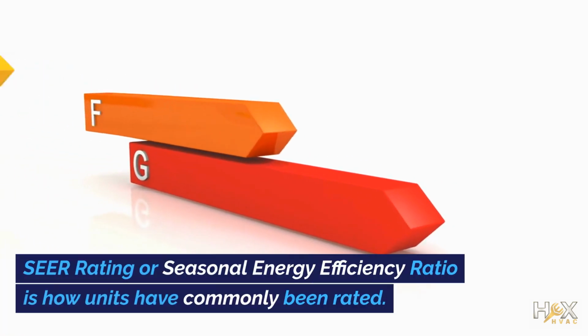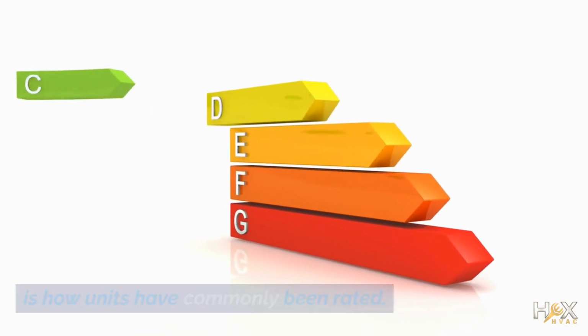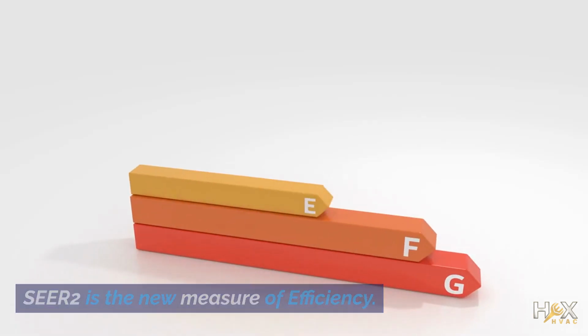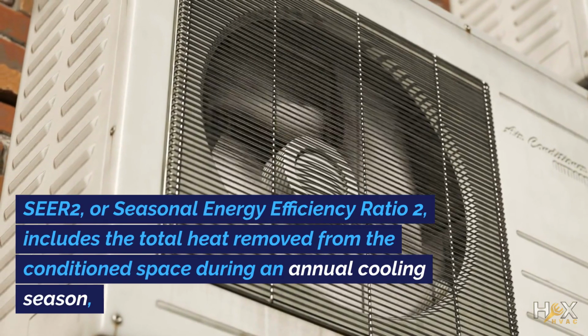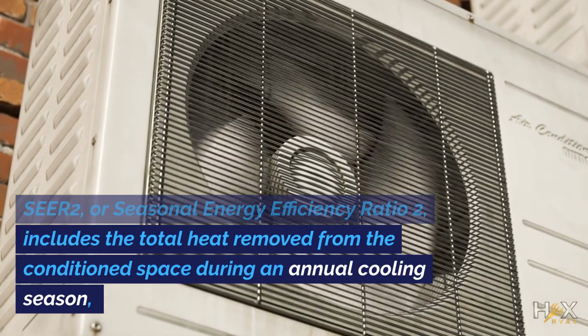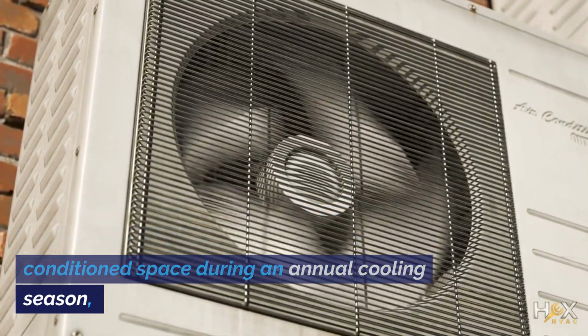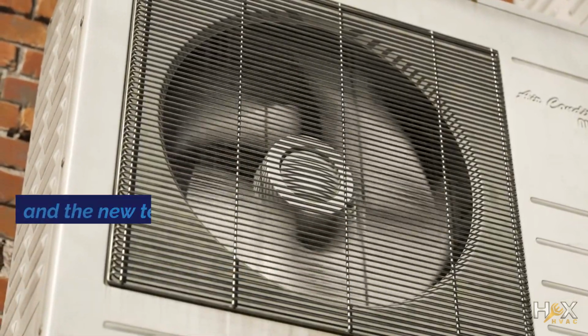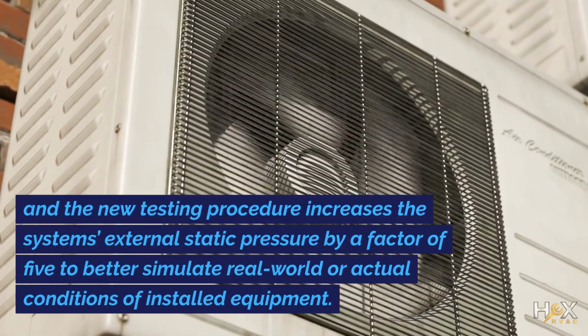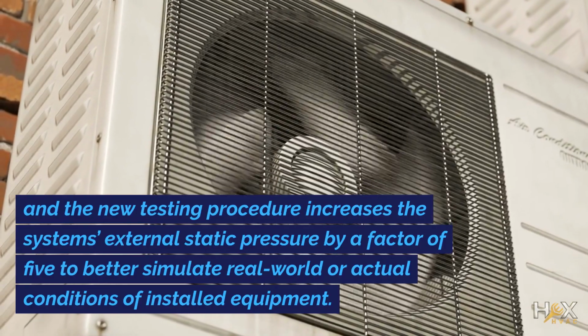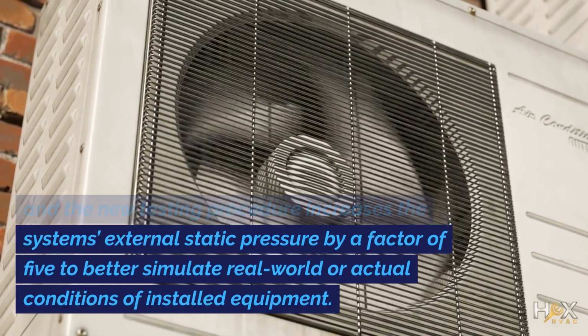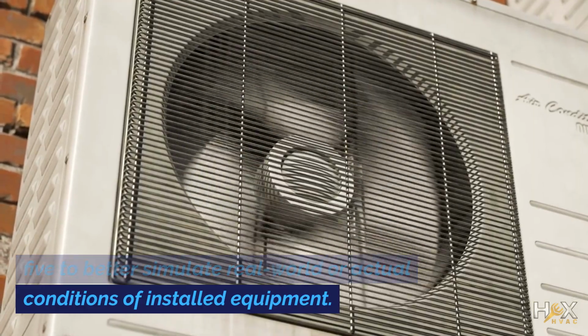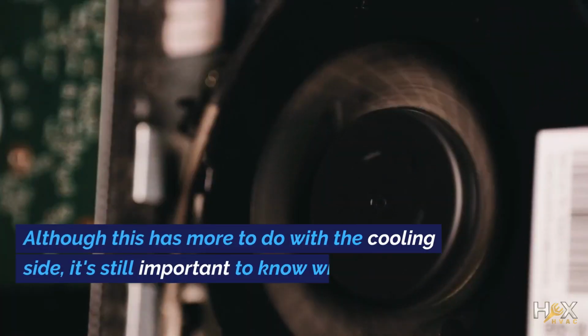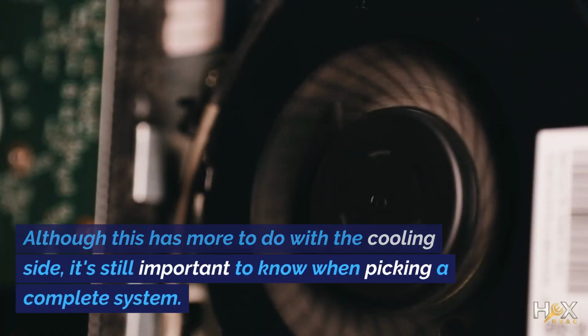Efficiency ratings: SEER rating, or Seasonal Energy Efficiency Ratio, is how units have commonly been rated. SEER 2 is the new measure of efficiency, including the total heat removed from the conditioned space during an annual cooling season. The new testing procedure increases the system's external static pressure by a factor of 5 to better simulate real-world conditions of installed equipment. Although this has more to do with the cooling side, it's still important to know when picking a complete system.